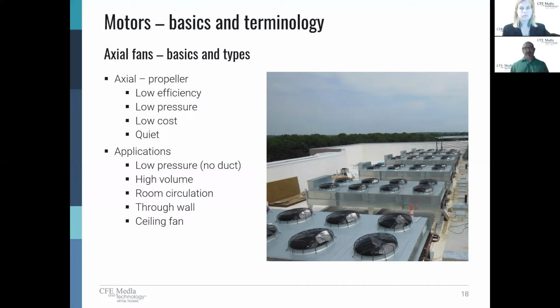One of the main challenges that I had with the condensing unit was trying to make it quiet because these fans can be kind of noisy. And if I want to enclose a condensing unit, I have to be very careful about the amount of static pressure that I'm going to impart on those fans. Because if I impart too much static pressure, they actually slow down, they don't get their efficiency, and therefore we don't get adequate cooling.